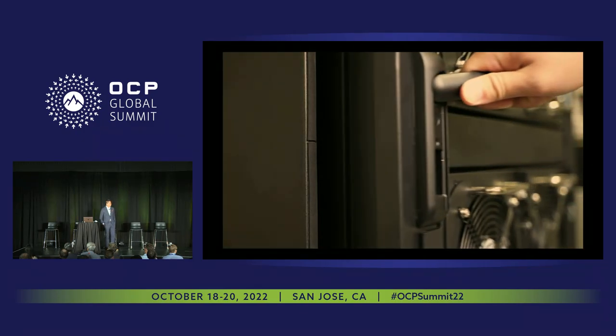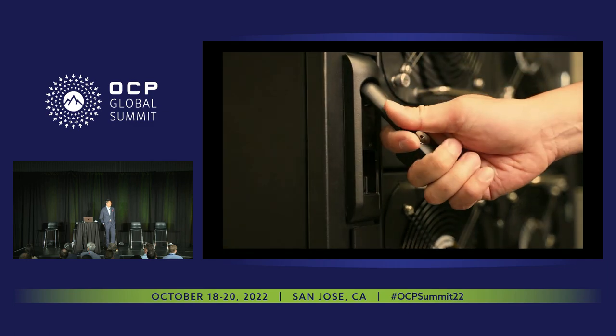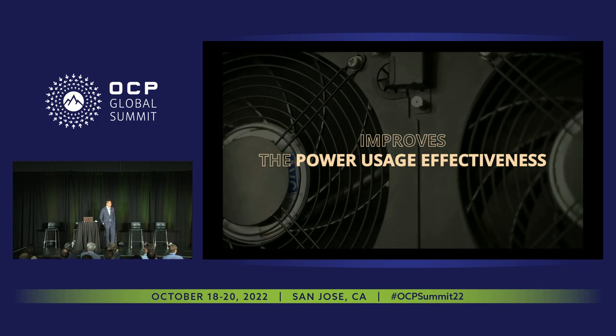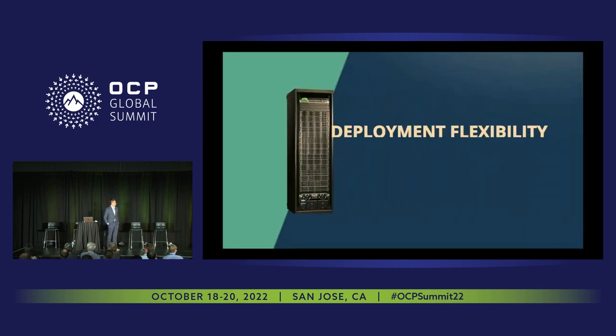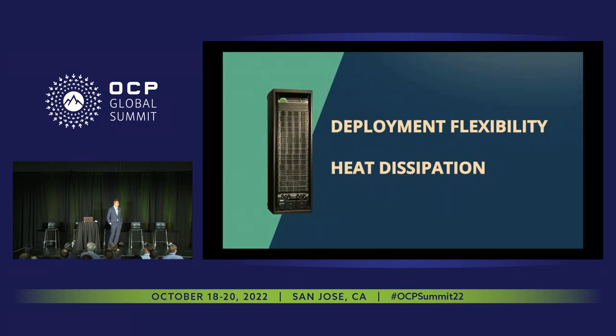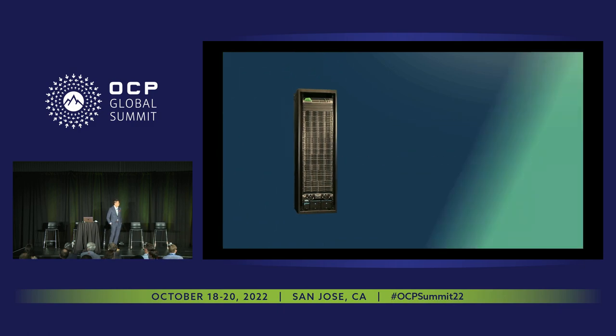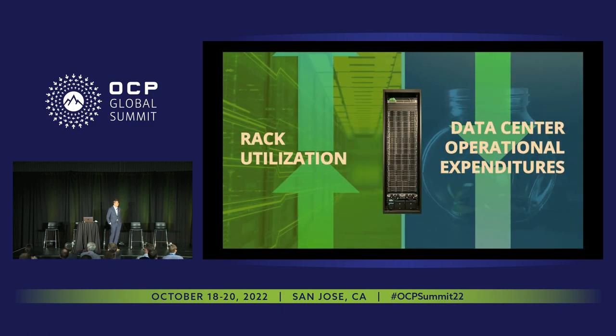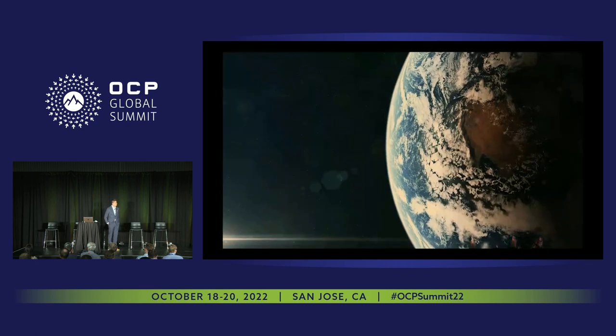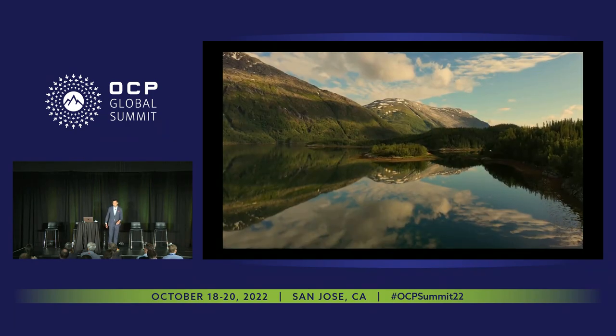The fan zoning feature of the QCT liquid cooling solution effectively reduces fan duty, which improves the power usage effectiveness, or PUE. Aligned with QCT's deployment flexibility in liquid-to-air heat dissipation, rack utilization goes up as data center operational expenditures go down, which in turn helps our planet and environment.